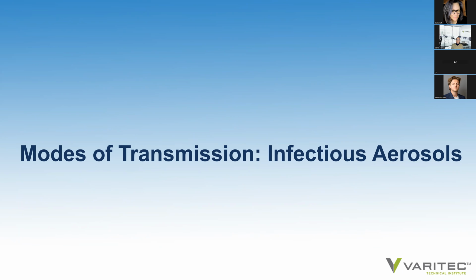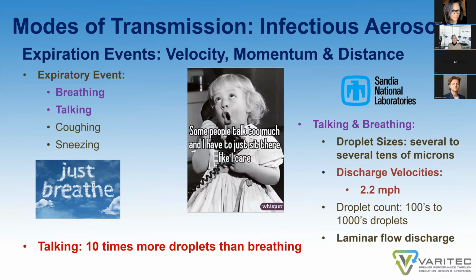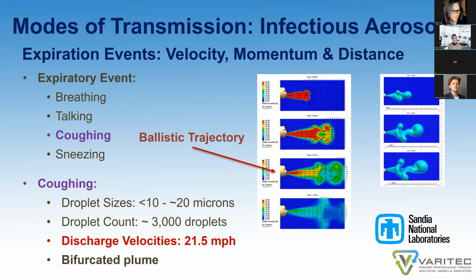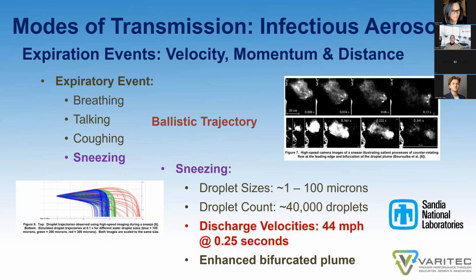So let's review the modes of transmission, a topic I've covered a number of times, certainly during the pandemic, but it's very important when we start reading the opening portion of ASHRAE Standard 241. The means of transmission of COVID-19 occur when an infected agent is breathing, talking, coughing, or sneezing. If somebody's talking, they release 10 times more droplets than simple tidal breathing at a work desk. There's coughing that offers a ballistic trajectory where aerosolized droplets with viral loads can project 15 to 20 feet in a space. Then there is sneezing, where these virally laden droplets can be projected 25 to 28 feet in a space.